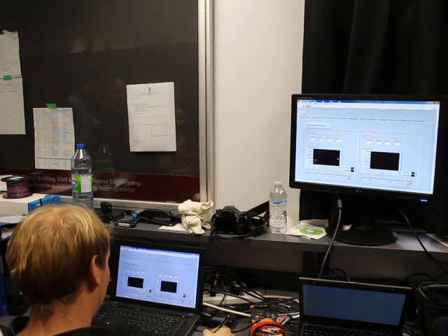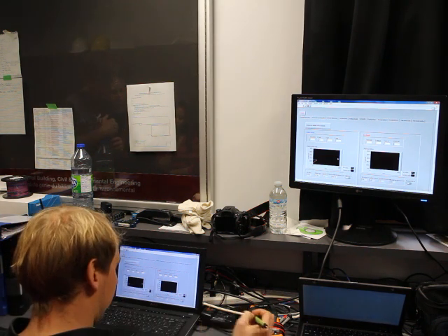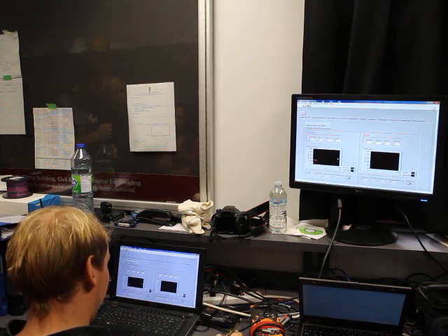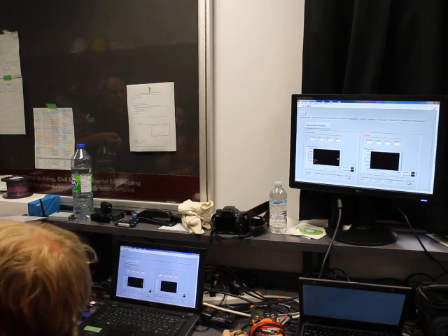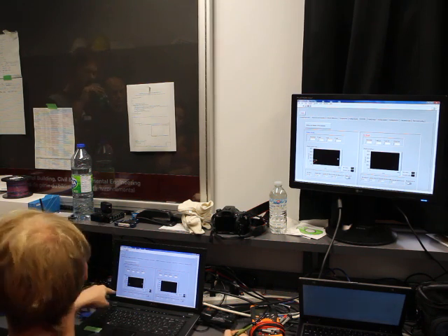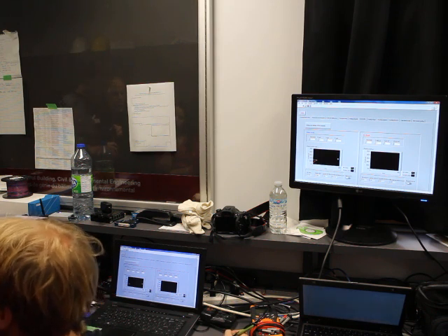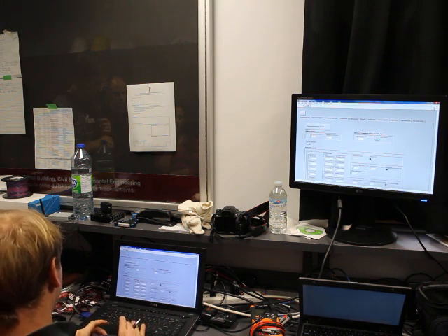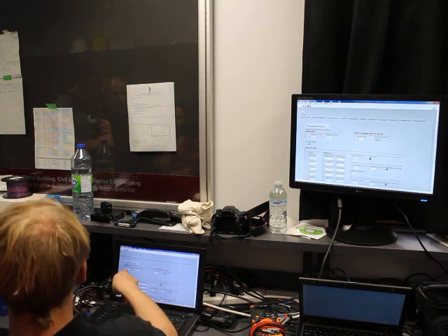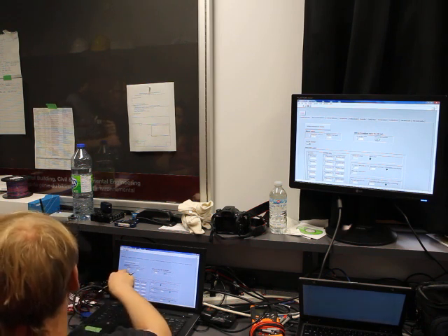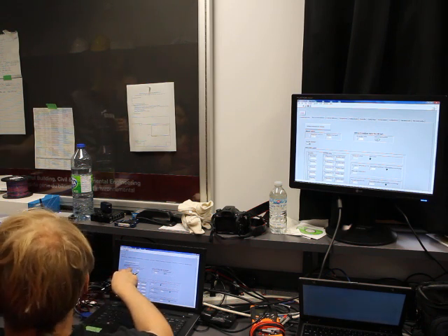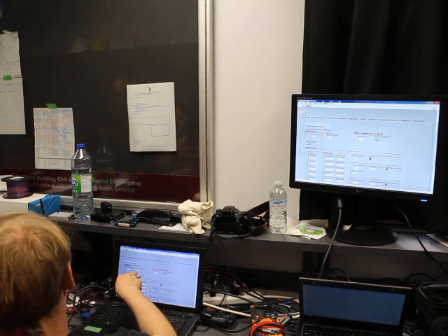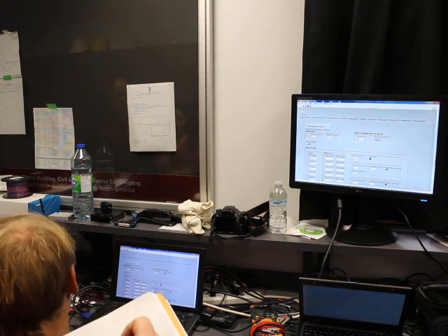Okay, so the standard is saying we need a mass flow of 0.02 kilogram per second per square meter. If we have a 2 square meter collector, that means 144 kilograms per hour. So maybe going back now a bit, I set the inlet temperature. At the moment we are at manual control, we call that. We set the temperature at 20 degrees C and 144 kilograms per hour.